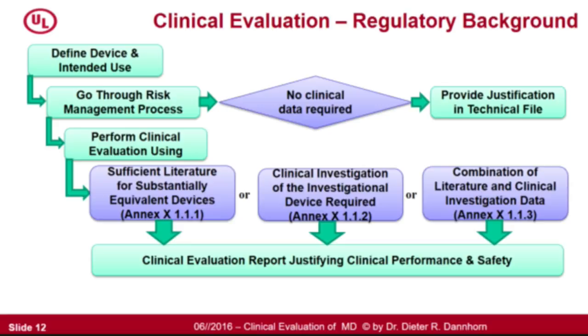It's only because in the current guidelines there is an old MDD referred to, and now they want to change it to the MDR. We hope there are no big new requirements inside, because the existing requirements are already very, very hard. So you need to define the intended use, go through a risk management process, and determine if clinical data is required. If not, justify that. Then you'll need a clinical evaluation, really pulling all of that information together.